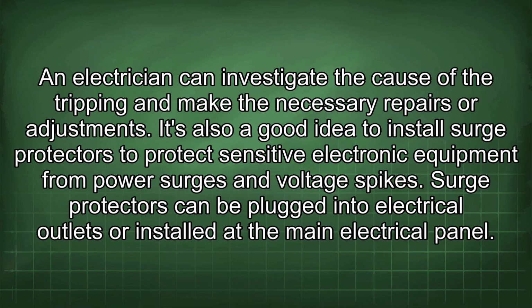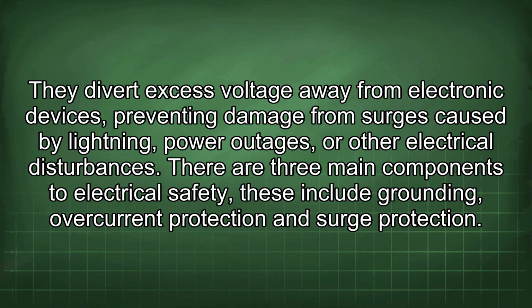It's also a good idea to install surge protectors to protect sensitive electronic equipment from power surges and voltage spikes. Surge protectors can be plugged into electrical outlets or installed at the main electrical panel. They divert excess voltage away from electronic devices, preventing damage from surges caused by lightning, power outages, or other electrical disturbances. There are three main components to electrical safety. These include grounding, overcurrent protection, and surge protection.